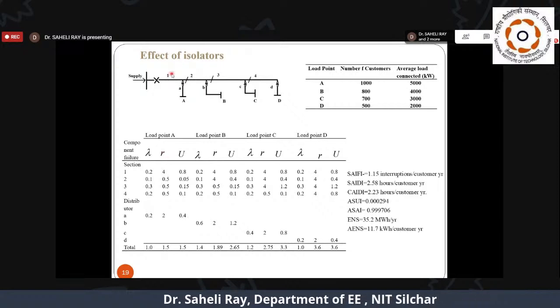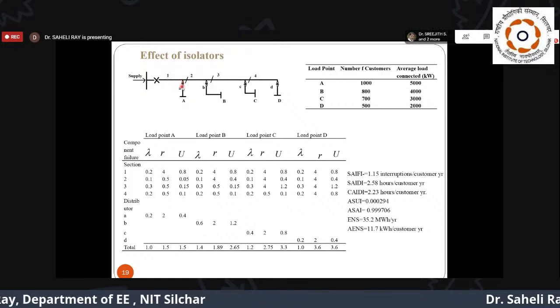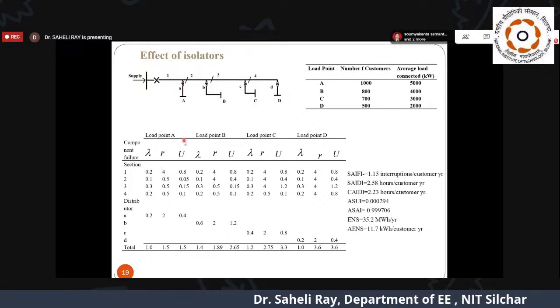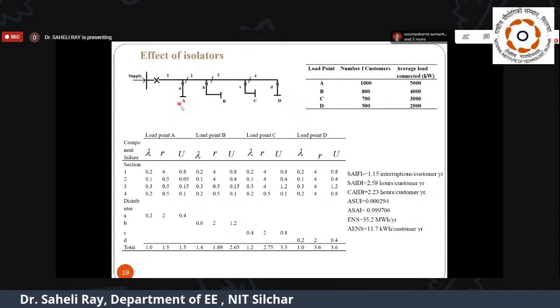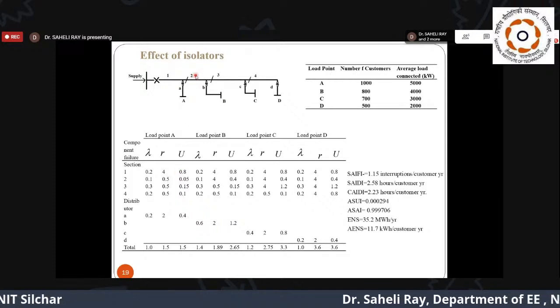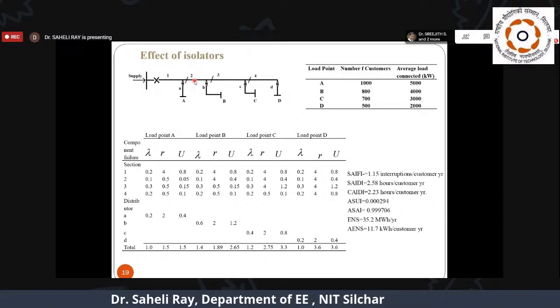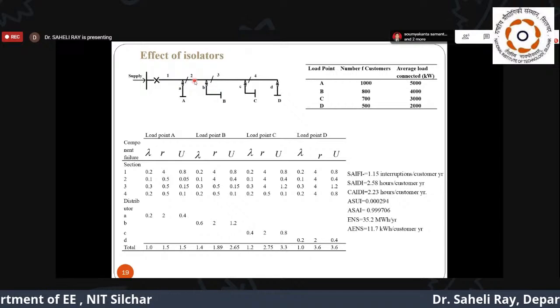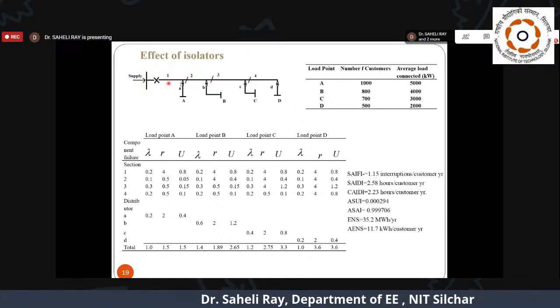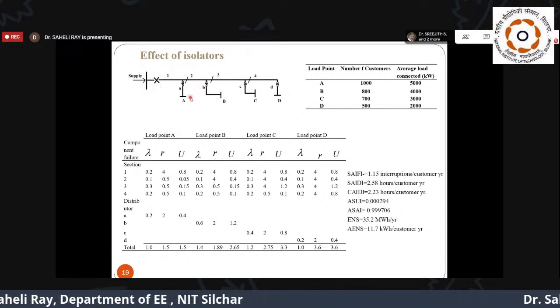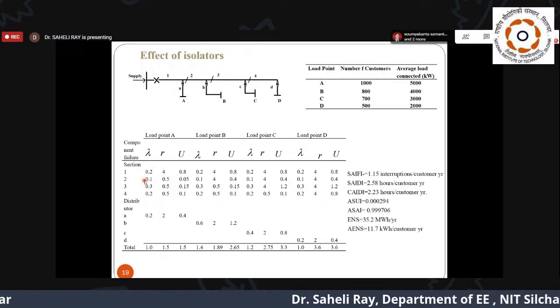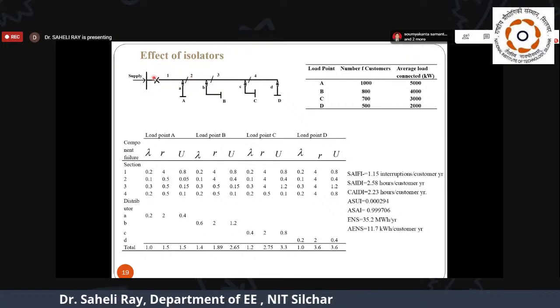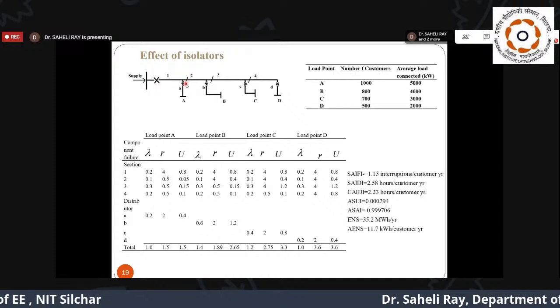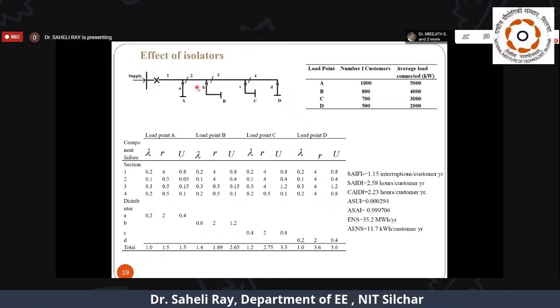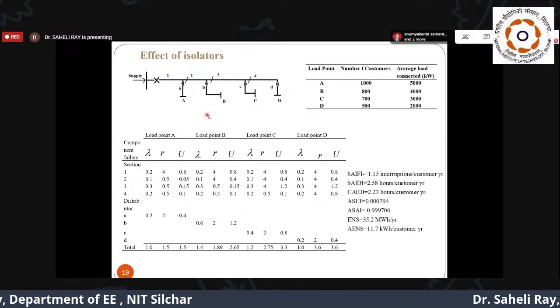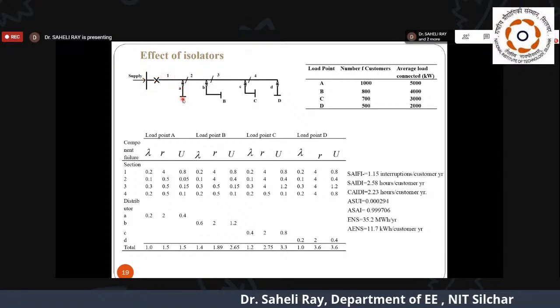So if a fault occurs in segment 1, then the system will be affected as earlier. I mean, failure rate will be 0.2, and unless and until the fault is repaired, we cannot resume power to point A, so the repair time will be 4. But whenever a fault occurs in segment 2 here, this will have some different impact from the previous discussions because of the presence of these isolators. What will happen? The moment a fault occurs at this point, the circuit breaker will trip. So every time power will be interrupted. As a result, the failure rate will remain the same, just as earlier. But once the circuit breaker operates, after that, by operating these switches, the faulty portion in segment 2, this total portion, can be isolated from the remaining portion and power can be restored to point A.